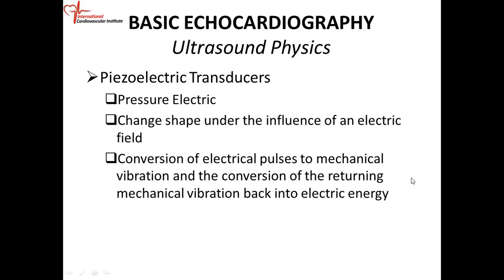The transducer is a piezoelectric transducer, and what we mean by that is it has these crystals, the piezoelectric crystals. The other term for it, or what it means, is pressure electric. That's what piezoelectric means. When it's under the influence of an electric field, it changes the shape of the crystals. And what you're actually doing is converting electrical energy into mechanical, that is sound energy. So the conversion of the electrical pulse to mechanical vibration of the crystals.